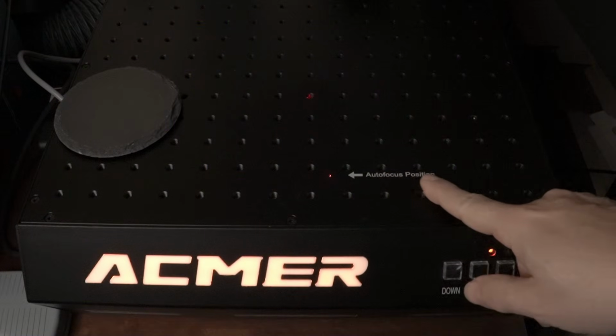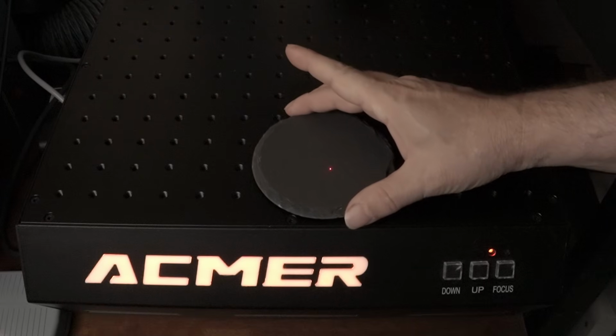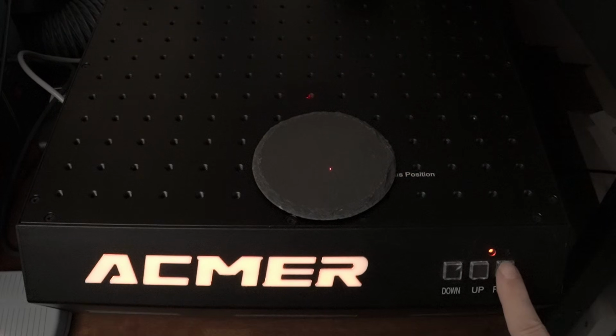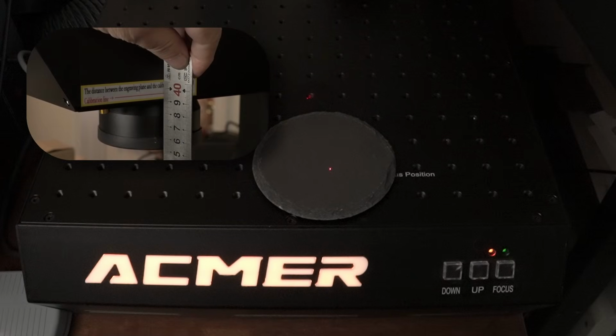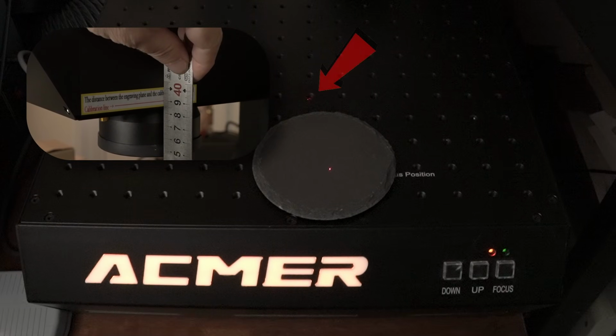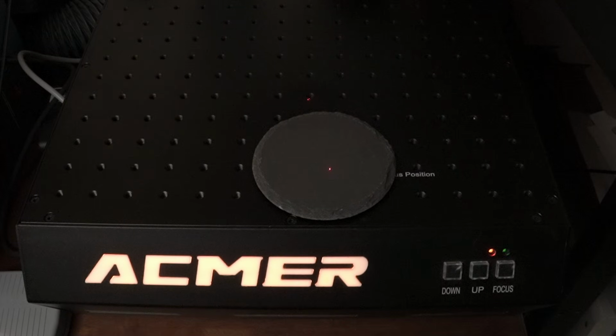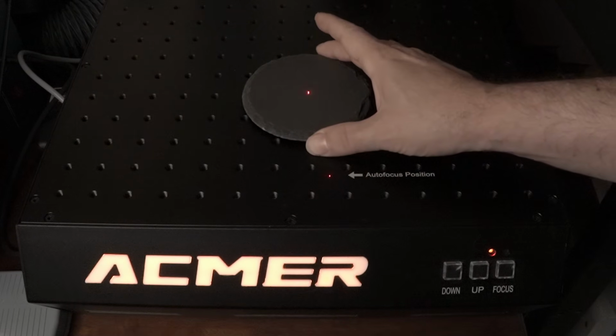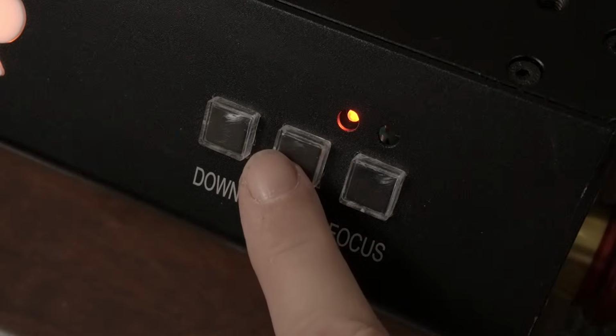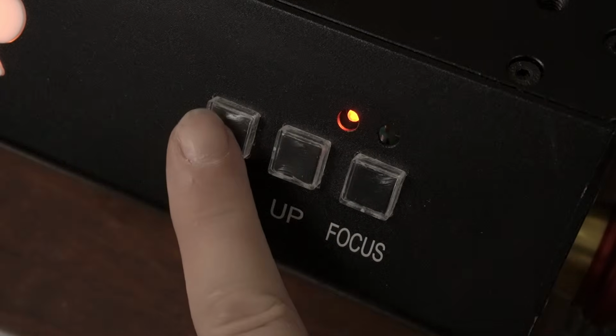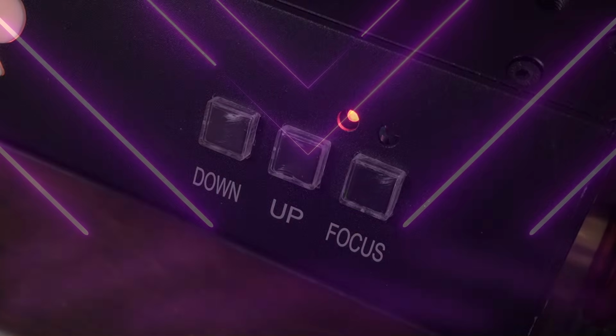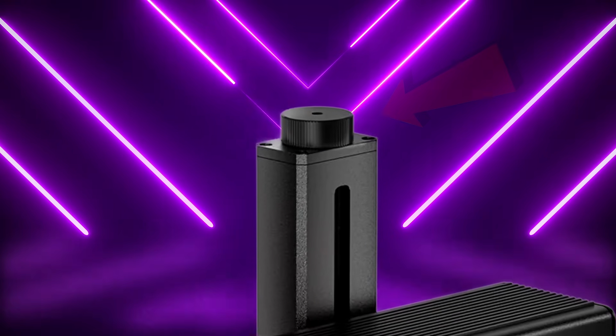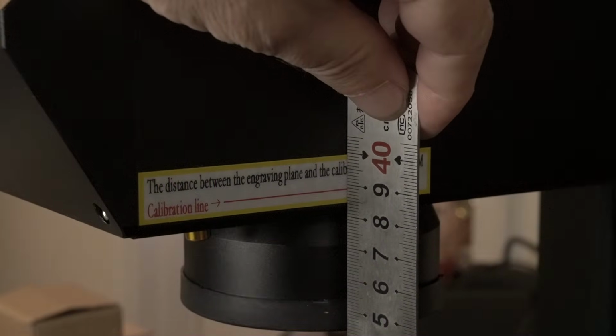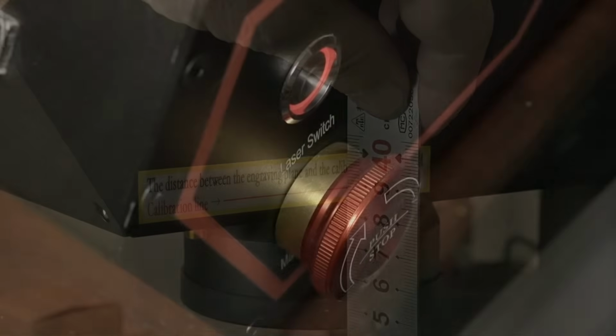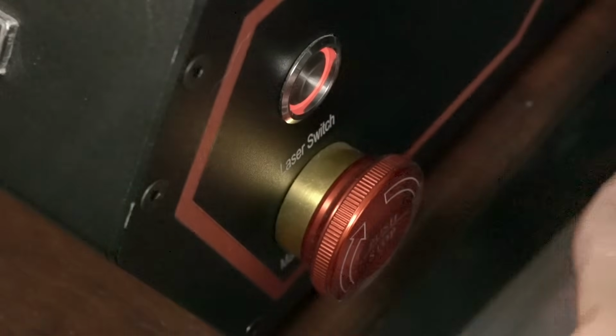This machine also comes with autofocus. Just place your material under the single red dot where the autofocus position is marked, and hit the autofocus button. As the head adjusts, the two guide lasers will converge into a single point when the machine reaches the correct focus. You can also focus the machine manually. You can do that electronically using the up and down focus buttons, or you can adjust it directly with the focus knob on the top of the machine. For this setup, with the 300mm lens installed, the correct focus height is 38.9 centimeters. On the side of the machine there's a power button and an emergency stop switch.